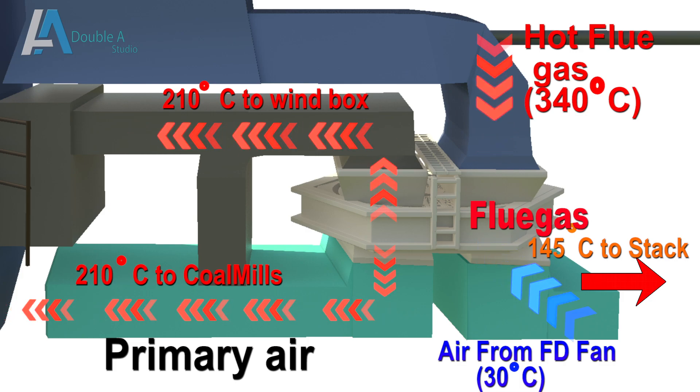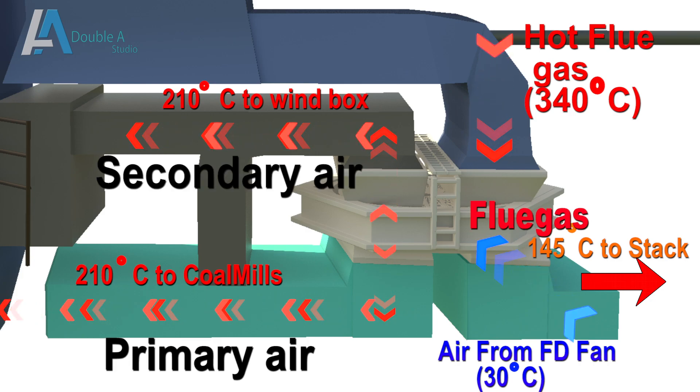Hot primary air is sent to pulverizer by primary air fan. It dries coal and transports powdered coal to furnace. It also reduces lump formation of powdered coal. Secondary air goes to combustion chamber through wind box. It promotes fast and complete combustion of fuel.